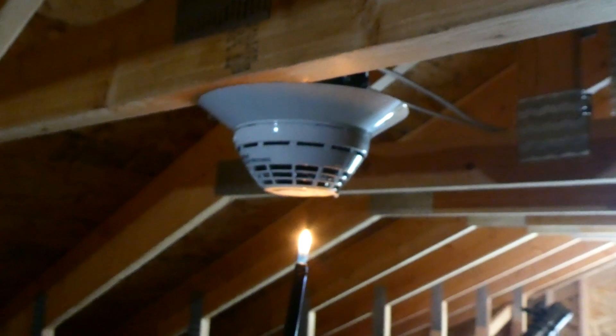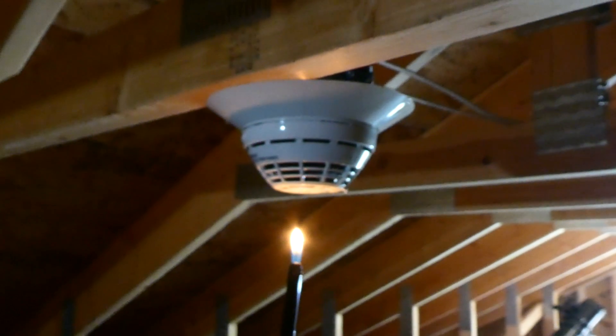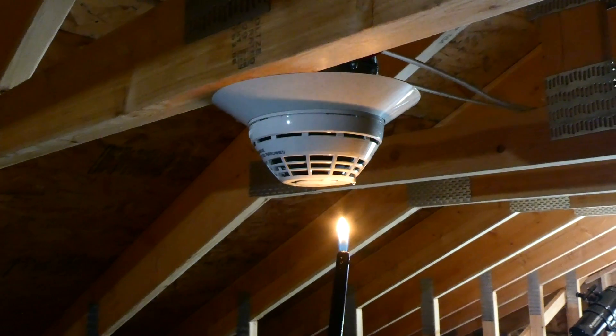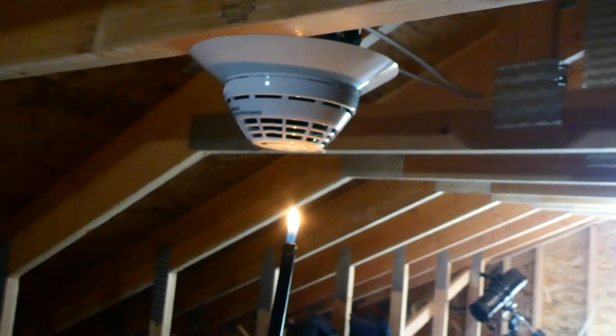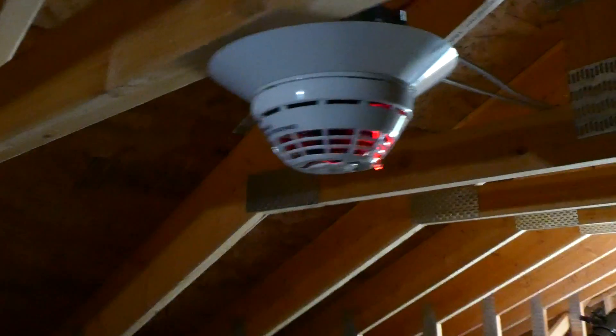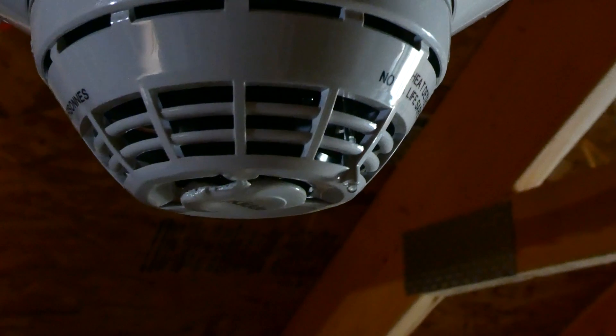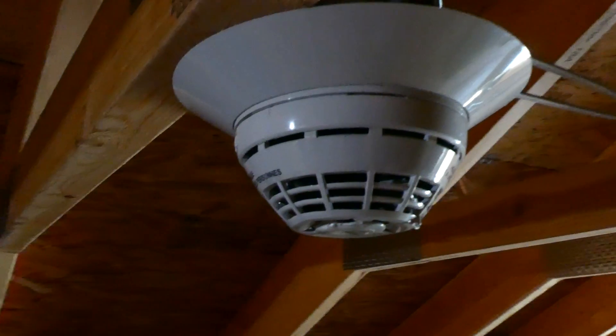Hello everyone. It's time for the next SCR system test. To start the video, we're going to be testing the heat detector that I have placed up here in the attic. It takes a second to activate. And as we can hear, the system did just go into alarm, and the light on the heat detector is flashing red, indicating that the heat detector is in alarm. So let's go on down and see the alarms.